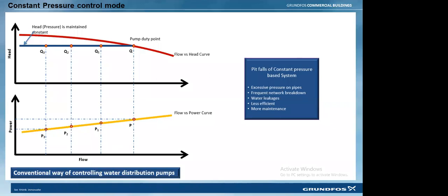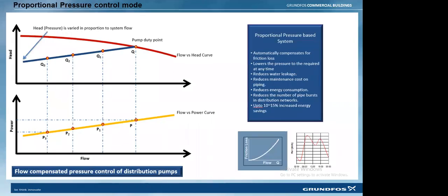So in the new generation system, how are we addressing this issue? Can you move to the next one? Instead of a constant pressure control, we have now come up with what is called proportional pressure control. In proportional pressure control, we take the flow and the operating pressure as references. With both references, we can have better control of the system. So how do we get more control on the system?